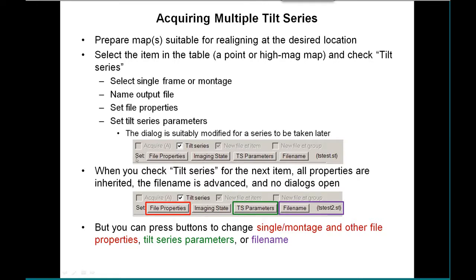Once you get through all those dialogs, this is what things look like in the upper part of the properties section with all these buttons enabled. The nice thing is you can check tilt series for your next location without going through all the dialogs again, because all the properties get inherited and the file name is advanced automatically. For example, if it was 'TS test,' it turns that into 'test 2'; if you had '1' or '1a,' it becomes '2' or '2a.' If you do want to change something, just press one of the buttons to change the file properties, whether it's single file versus montage, the tilt series parameters, or the file name.